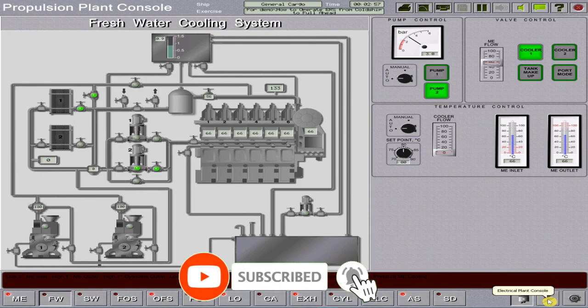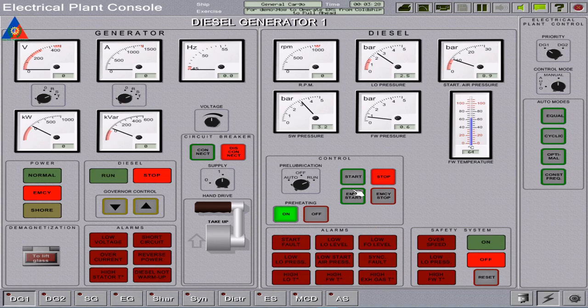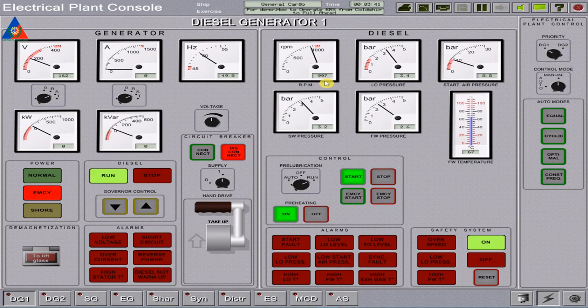Proceed back to the diesel generator number one panel and confirm all parameters are normal. We are waiting for the starting air to rise to around 8.5 bar. Once there is no more alarm on low starting air pressure, start the auxiliary engine by pressing the start button. Once generator number one has built up to rated RPM at around 997 RPM, with a steady voltage of 400 volts and at least 50 Hz, we can connect the generator to the bus bars by pressing the circuit breaker.